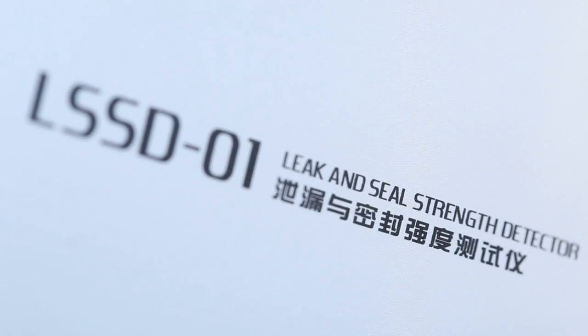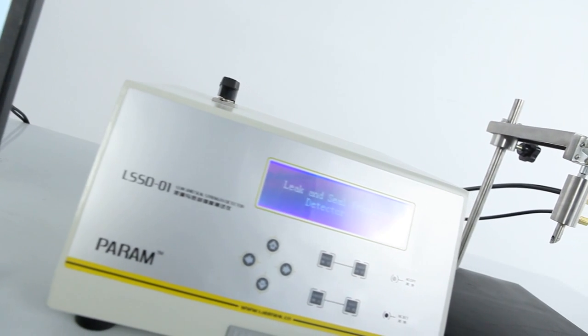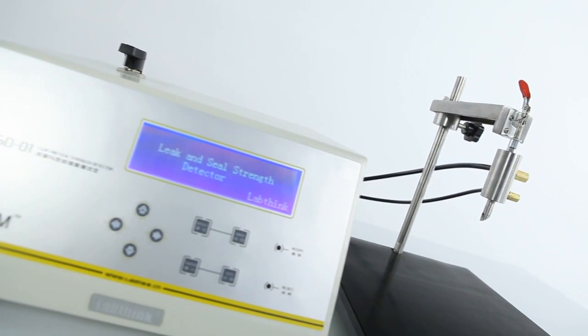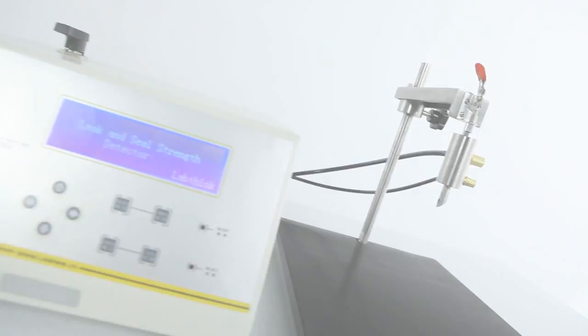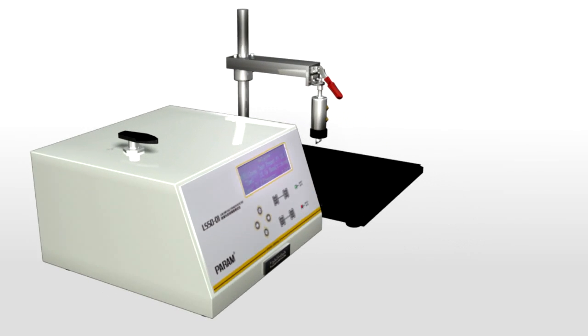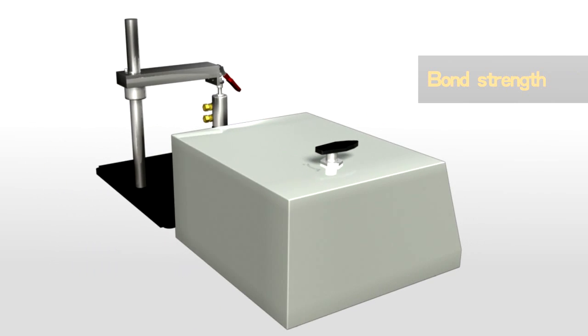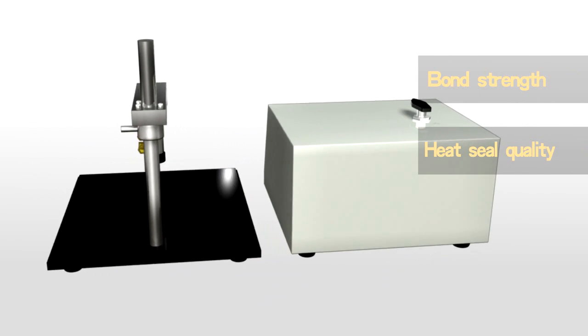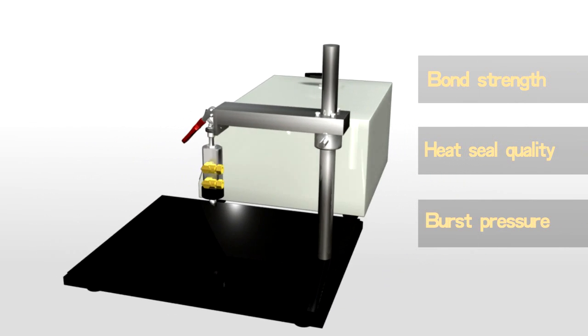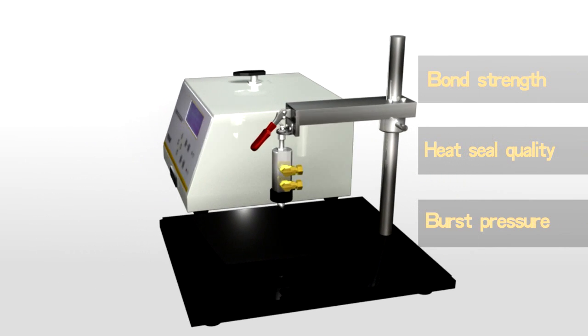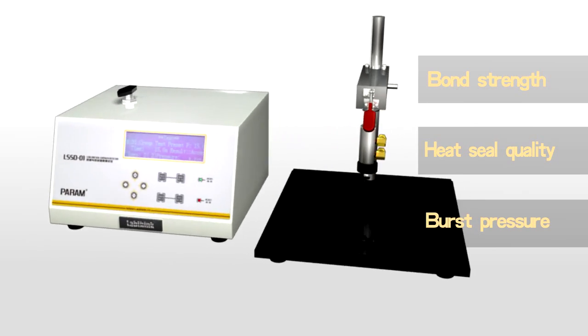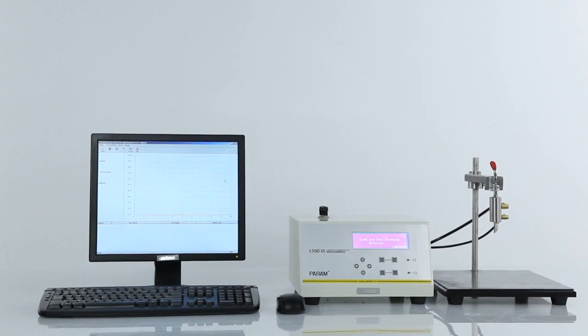LSSD-01 is a leak and seal strength detector that adopts the positive pressure method. It is broadly used for the quantifiable measurement of bond strength, heat seal quality of heat seal edges, and burst pressure of flexible packages, which are produced by heat seal processing and adhesive processing.